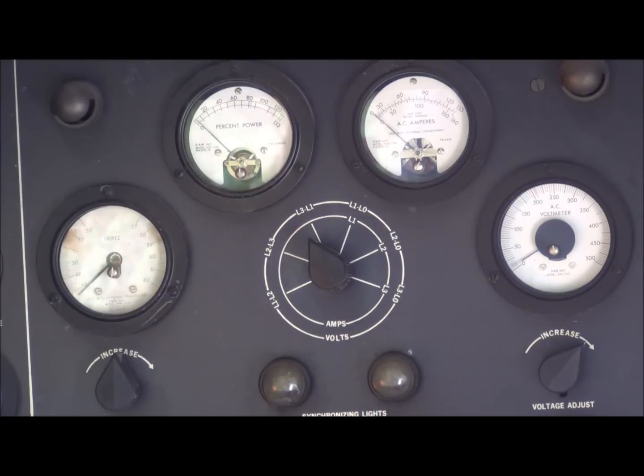Alright, now that we have our frequency meter repaired and we've taken care of the overvoltage trip problem, I went ahead and hooked up the load bank to the generator. Now what I'm going to do is just apply a few varying loads to the generator, and I'm going to just be checking for proper response. I'm going to be watching the meters, make sure that they're indicating the proper current and the proper overall power. And then I'll test the overload trips on the individual phases. So we'll hit it with some fairly large loads and make sure that the generator protective devices work as expected.